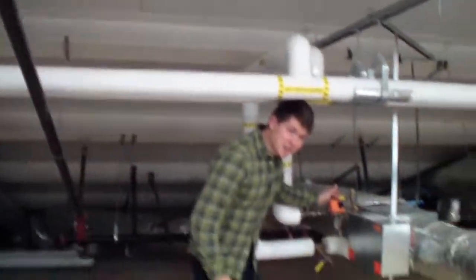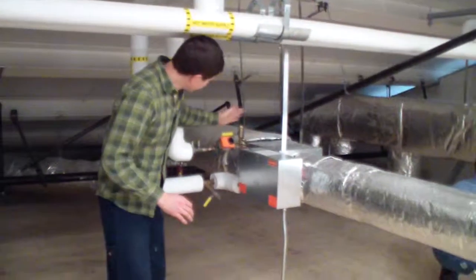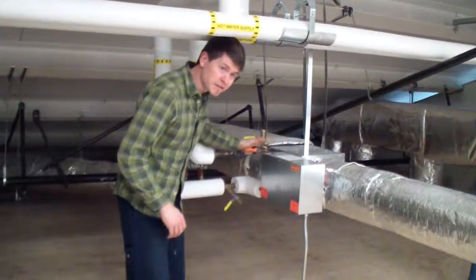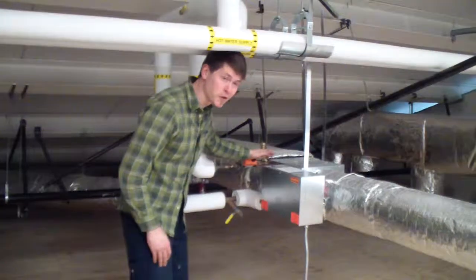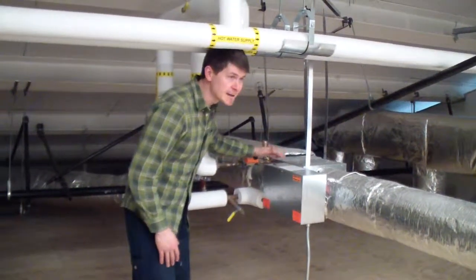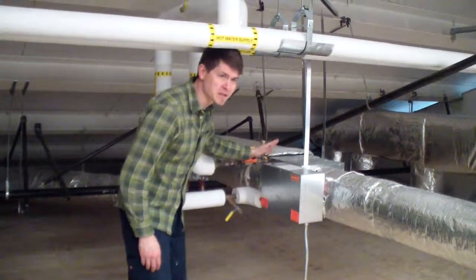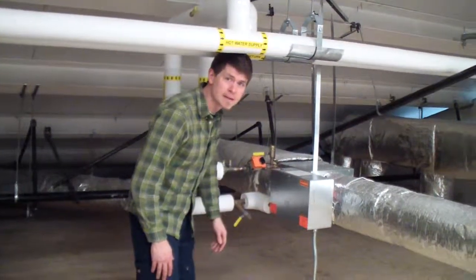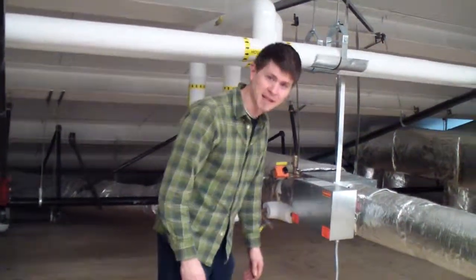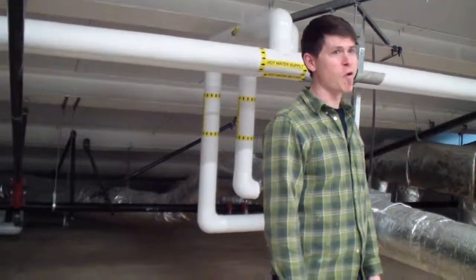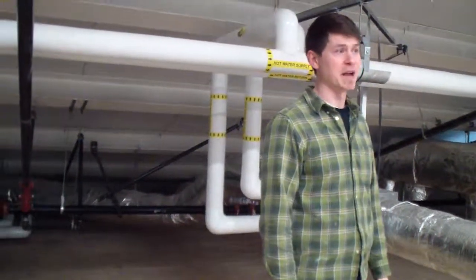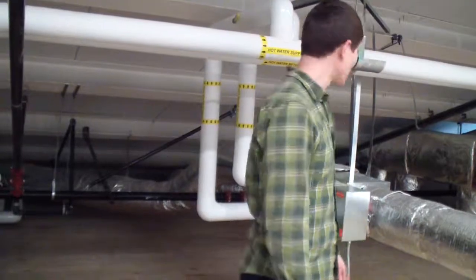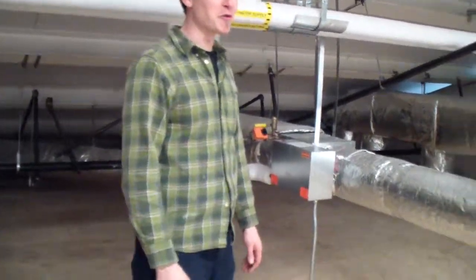Your reheat coils have their own valves on them. Perpendicular to the coil like this is off. If it's parallel with the coil itself and the piping, that means that it's fully open. And these do modulate, so anywhere in between, obviously, it's a percentage of water flow to the box itself. Based off of what the space temp is, that'll determine what percentage of hot water it wants to move into the space. They look like the balloon ones. Yes, yeah. I believe all the bright orange valves are actuators.